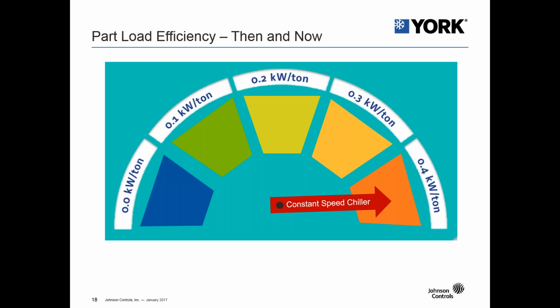So if we look at part load efficiency then and now, previously, prior to the advent of putting variable speed drives on chillers, a constant speed chiller at part load would be able to reach about a 0.4 kW per ton at part load. Then when adding a VSD to the centrifugal chiller and you're able to slow down the motor, we were seeing across the industry kW per tons as low as 0.2 at part load.